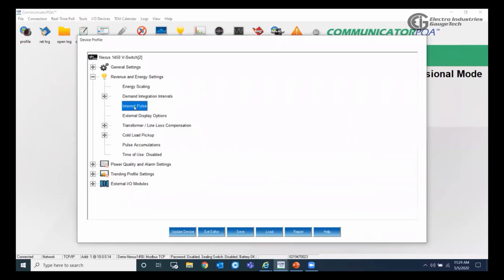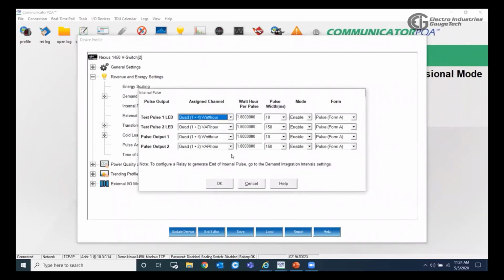The internal pulse, because this meter has 2 pulse outputs, and it has 2 test pulses, which can be used to test the meter. So this is where we can set up these test pulses, and we can choose one of these quadrant energy, and we can give the weight for that pulse. By default, it would be 1.8 watt-hour per pulse, but that can be changed, and we can set the pulse width based on the tester we are using. And we can choose between form A and form C.